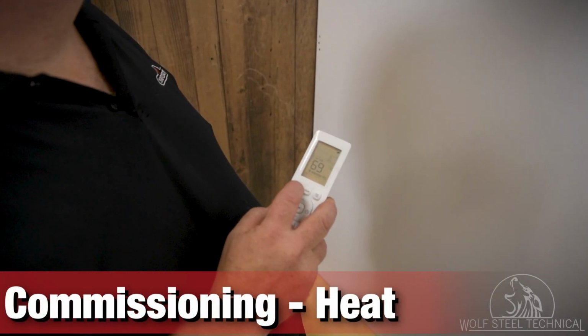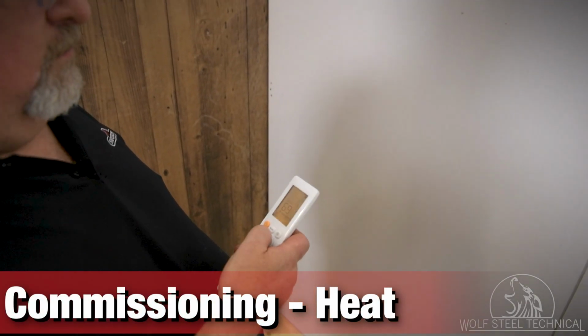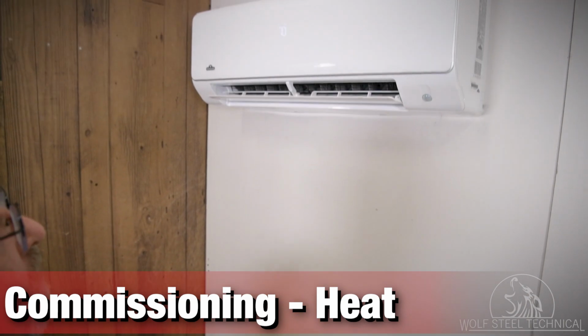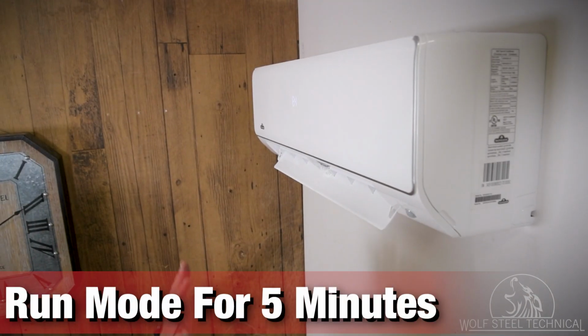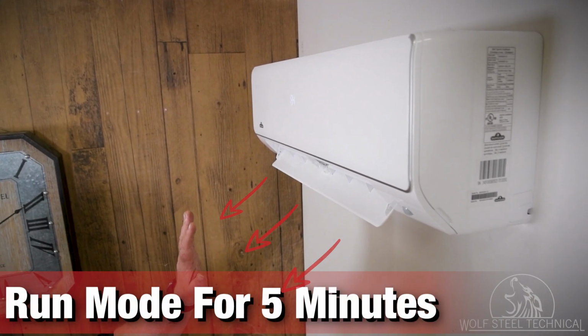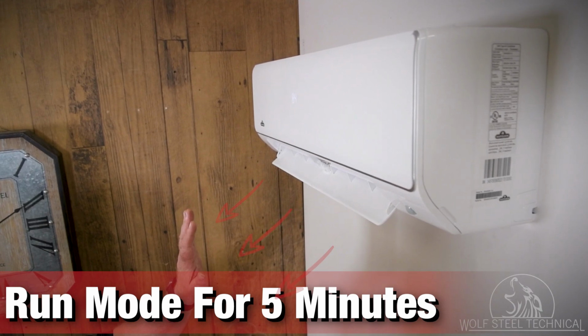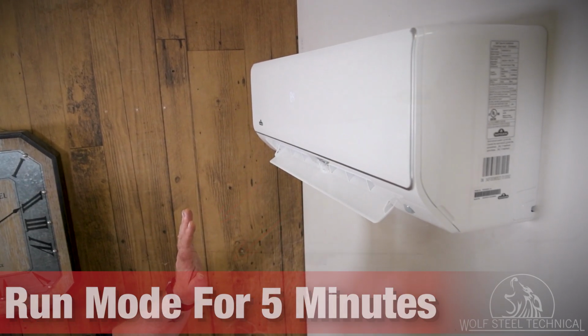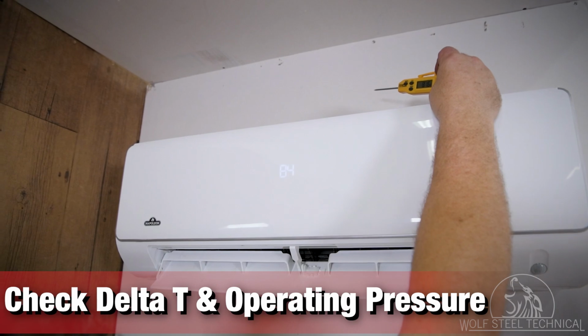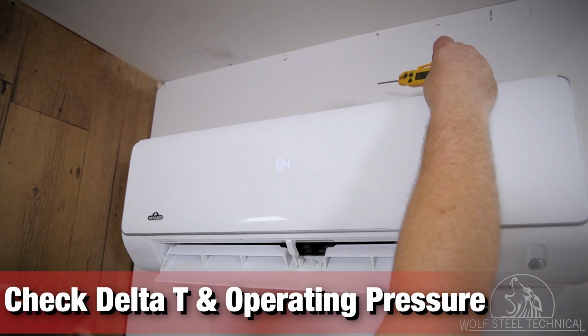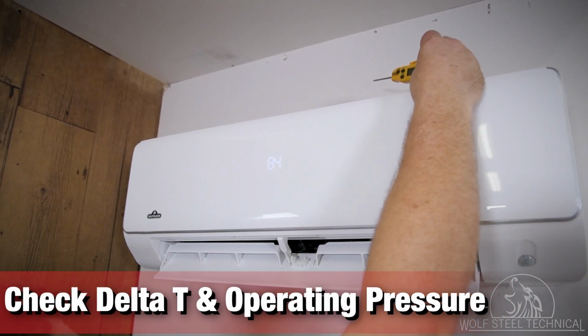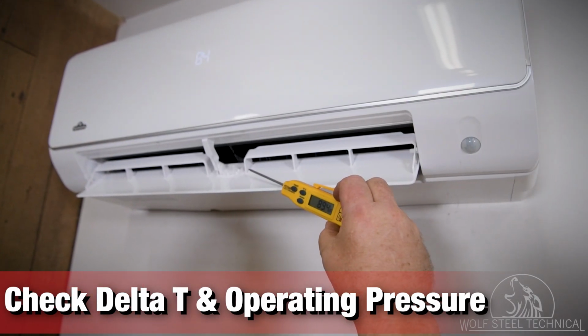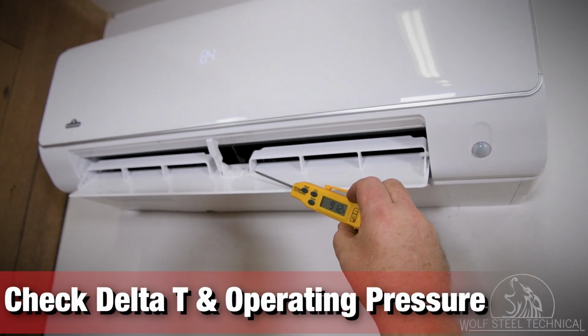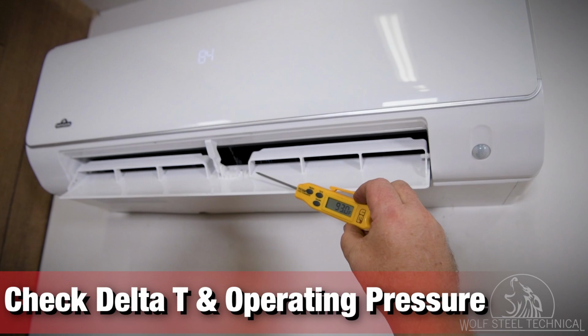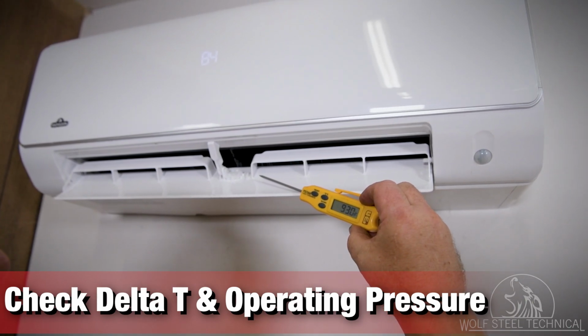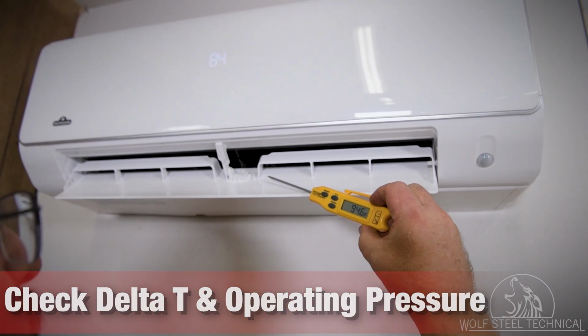Use the remote to turn on the system. Set it to heat, bumping the temperature up as high as possible. Run this mode for 5 minutes, ensuring the system is operating as intended, and hot air is being produced by the indoor unit. Check the delta T over the coil and the operating pressure to ensure it matches the values stated in the service manual. Heat rise values fluctuate depending on the ambient temperature outdoors. Observing a rise of approximately 15 to 20 degrees Fahrenheit is expected.